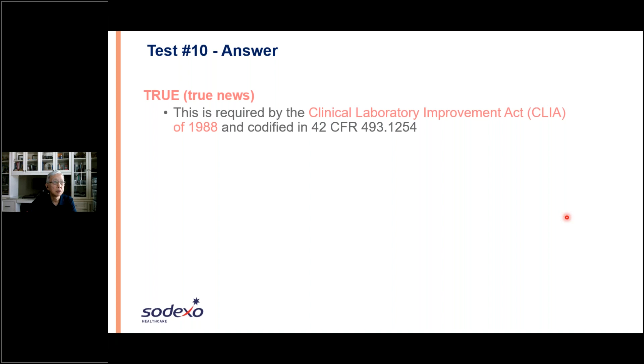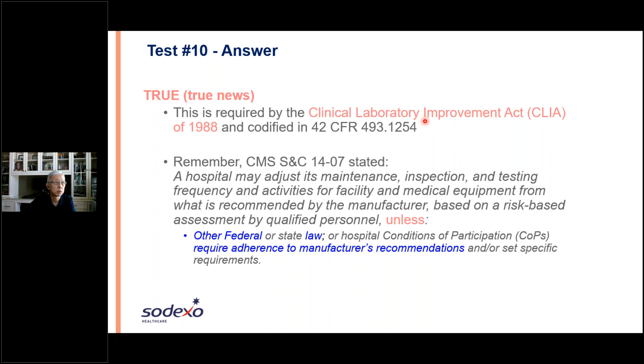And even the CMS in its 2013 memorandum said very clearly that you can adjust your maintenance, inspection, testing frequency, etc., unless there is other federal or state law or hospital condition of participation that requires adherence to manufacturer recommendation. Since this is a law, you don't have a choice. So be careful, my friends. Laboratory equipment has to be 100% performed and maintained per manufacturer recommendation.